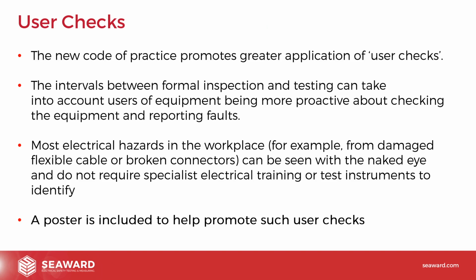The intervals between formal inspection and testing can take into account users of equipment being more proactive about checking the equipment and reporting faults. So when we're doing a risk assessment, or where the duty holder is doing a risk assessment, if the user is being proactive and doing very regular user checks, that can be factored in. And that's a factor they can include, and actually something that they really should include in there as another control measure to manage the electrical safety of equipment in the workplace.